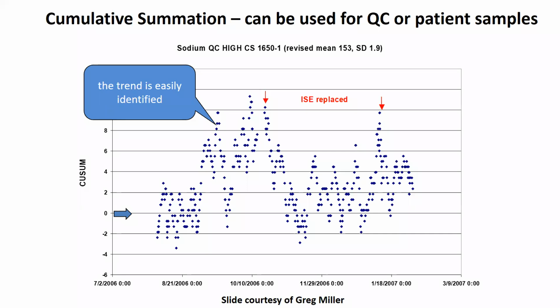Calculation of the sums of differences for QC values from a target mean is called cumulative summation. This is another powerful way to detect measuring system issues earlier than routine statistical QC. In this approach, the sum of the SDIs for a specified number of QC results is plotted. If the measuring system is stable, that sum should always be the same. However, if the sum shifts or drifts, as shown in this graph for sodium QC results, that means that an analytical measurement system problem may be developing.